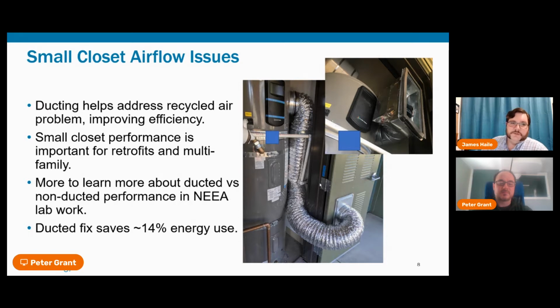The instructions note that if the ambient temperature in the cabinet drops 15 degrees during heating, air circulation is insufficient and the unit must be ducted. We typically saw a 20-degree drop in the first half hour of the heating cycle during our post-commissioning period, before occupancy, which is clearly much more of a drop than that criteria.